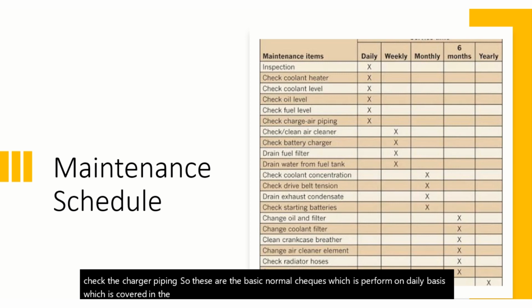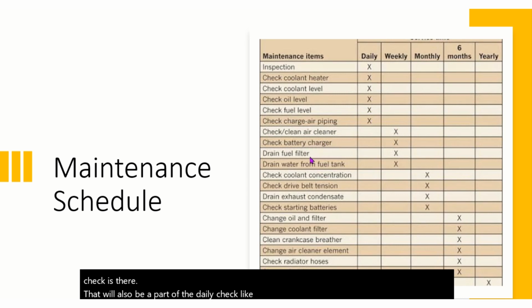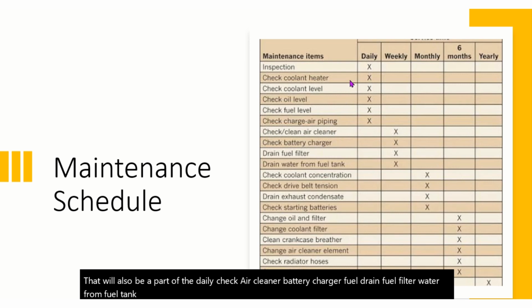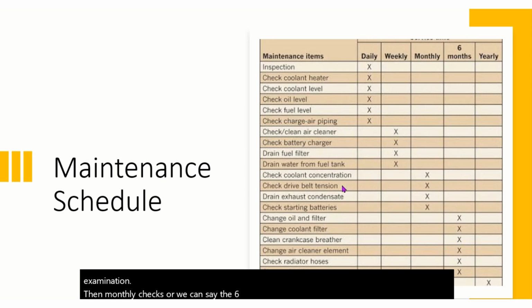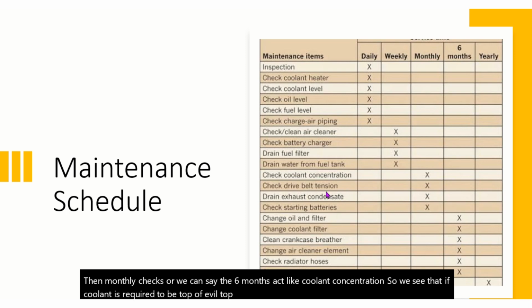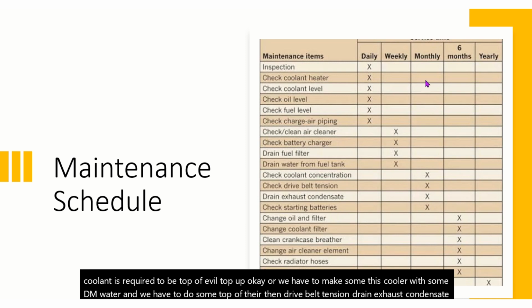Okay, whatever the weekly check is, that will also be a part of the daily check, like air cleaner, battery charger, drain fuel filter, water from fuel tank. All those are normal checks which are normally done through visual examination. Then monthly checks, or we can say the 6-month check, like coolant concentration. If coolant is required to be topped up, we will top up. We have to mix some of this coolant with some DM water, and we have to do some top up there. Then drive belt tension, drain exhaust condensate, all these parameters are what we do in monthly checks.